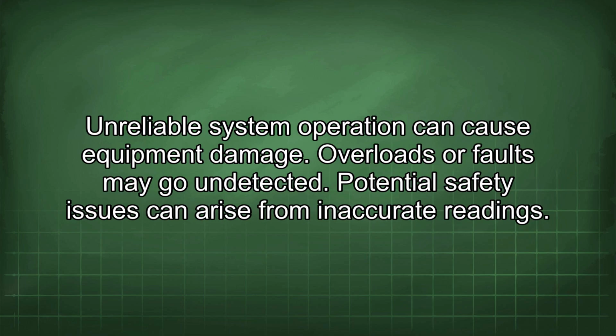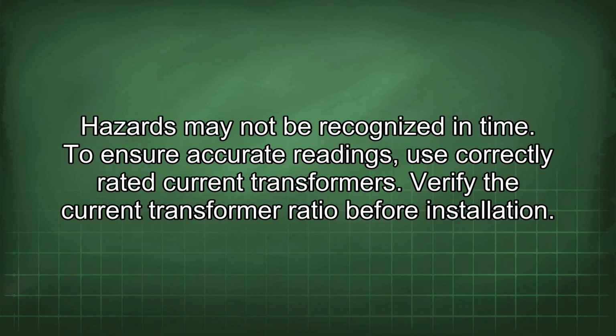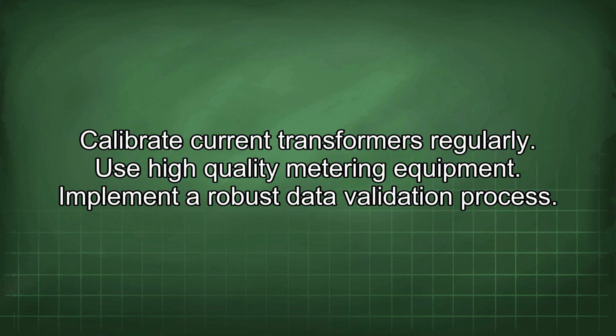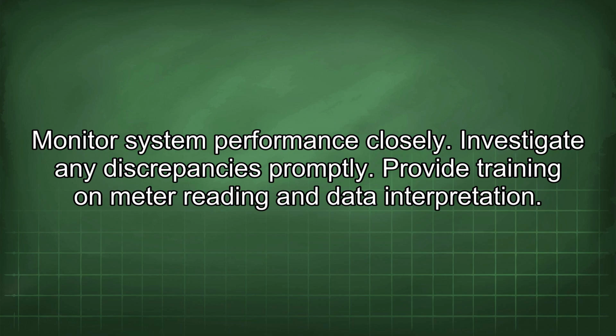Unreliable system operation can cause equipment damage. Overloads or faults may go undetected. Potential safety issues can arise from inaccurate readings. Hazards may not be recognized in time. To ensure accurate readings, use correctly rated current transformers. Verify the current transformer ratio before installation. Calibrate current transformers regularly. Use high-quality metering equipment. Implement a robust data validation process. Monitor system performance closely. Investigate any discrepancies promptly.